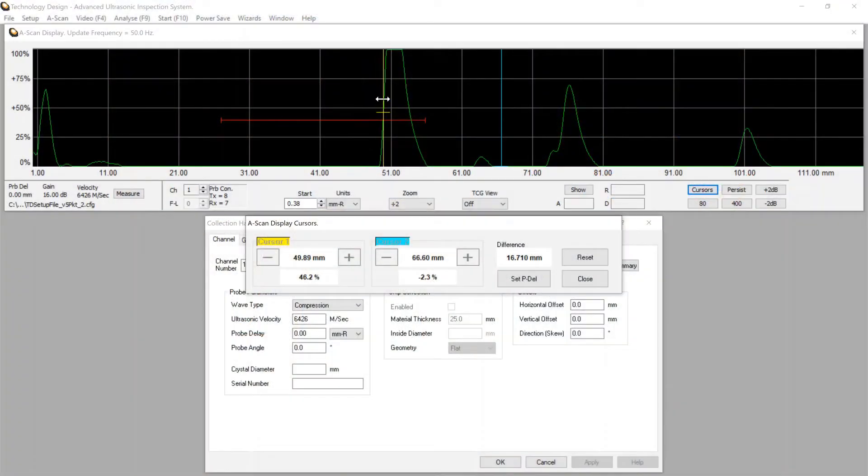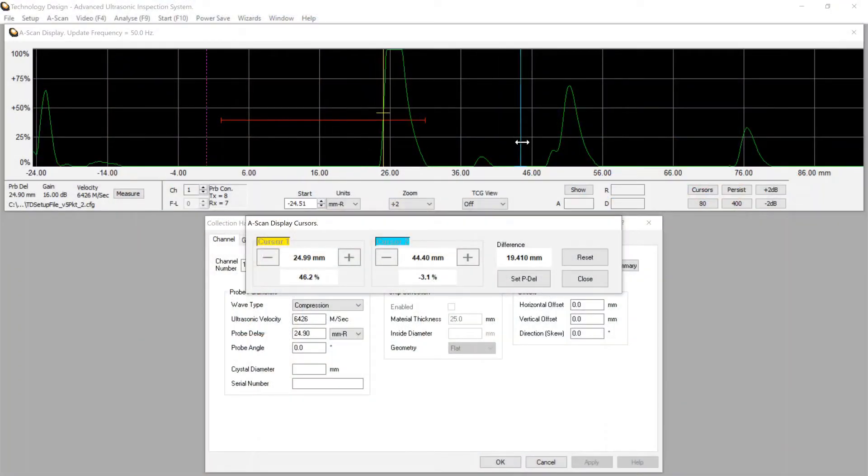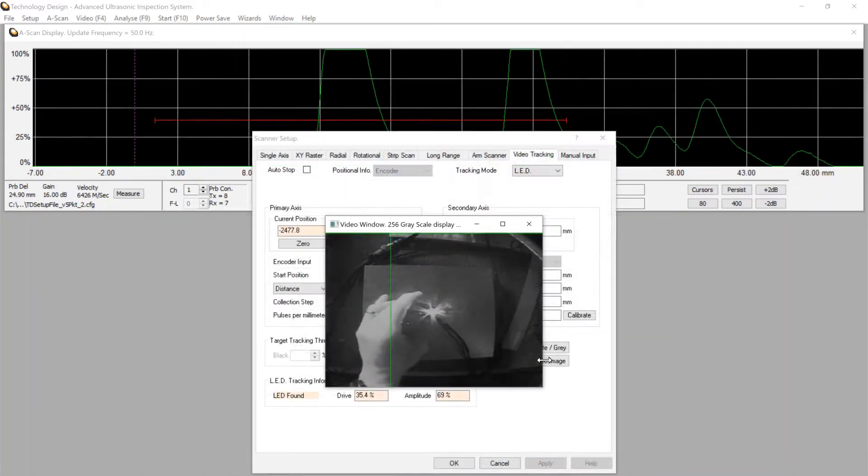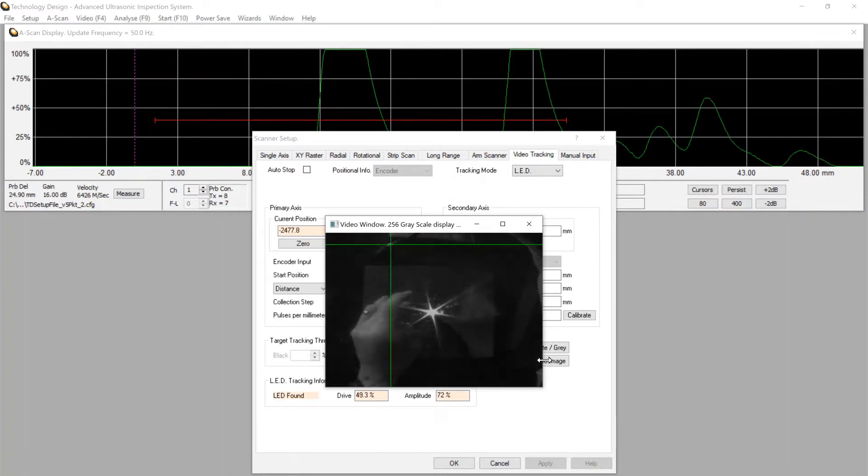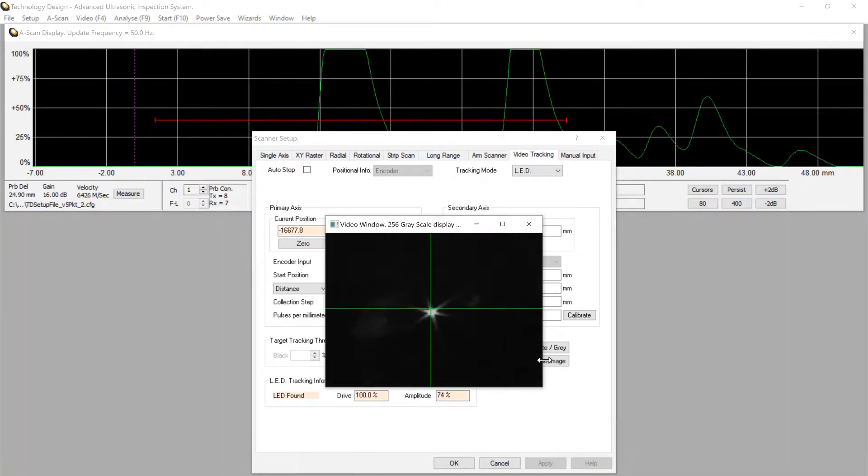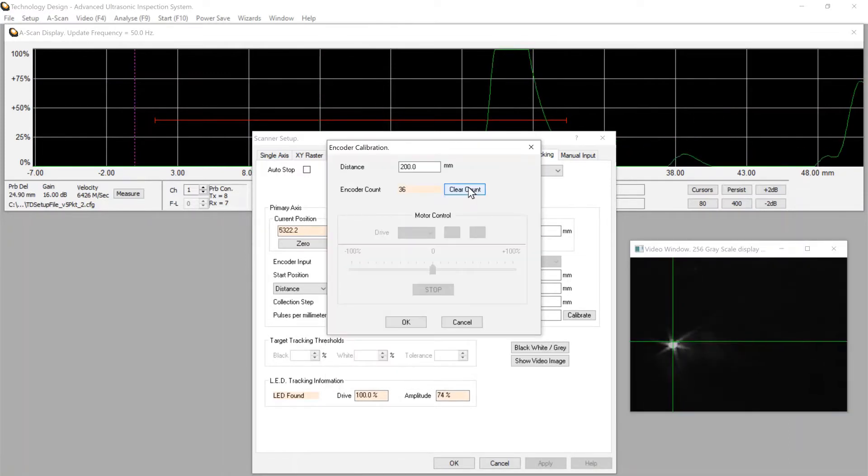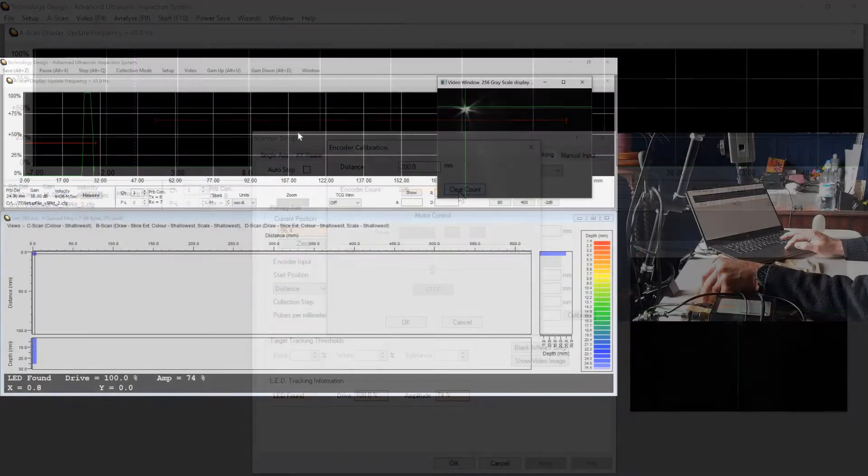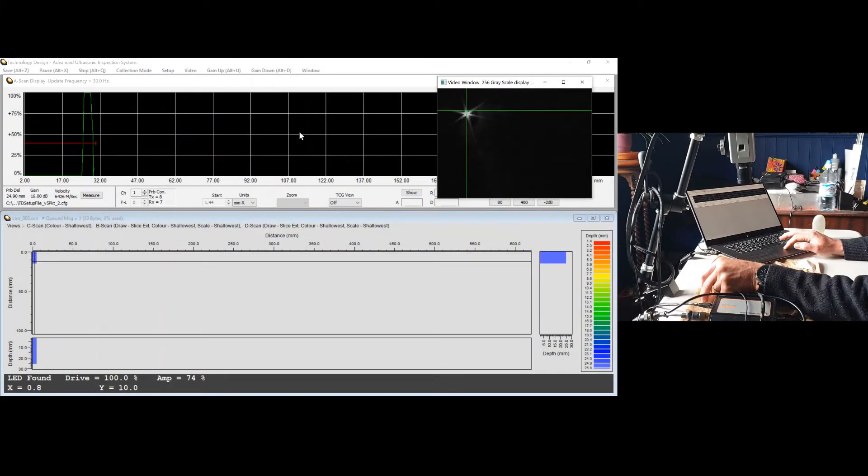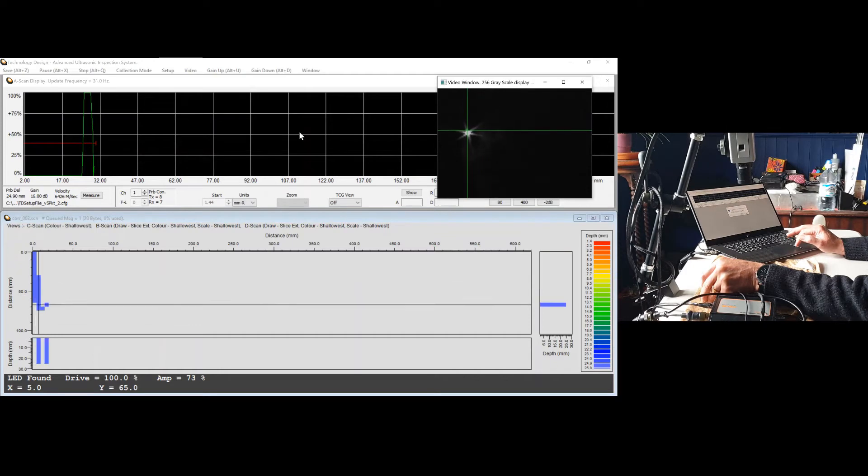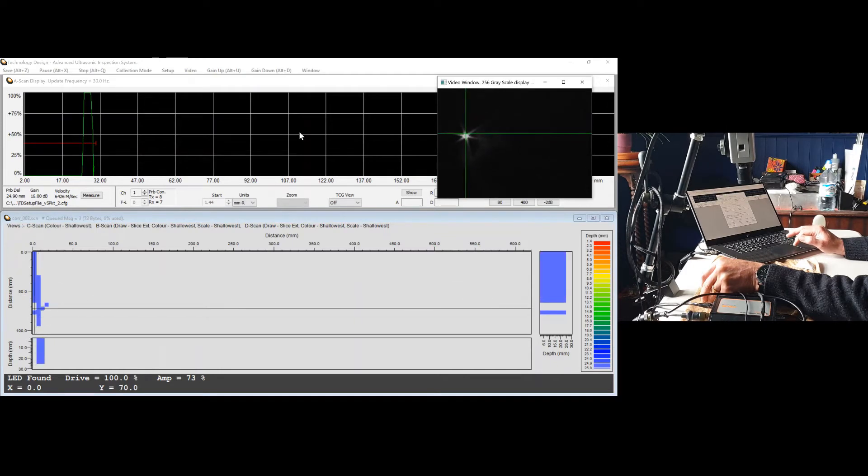The work first starts with routine UT configuration and calibration, followed by setup and calibration of the video tracking system. After setup and calibration, data acquisition begins by simply scanning manually in any direction, whatever is comfortable.